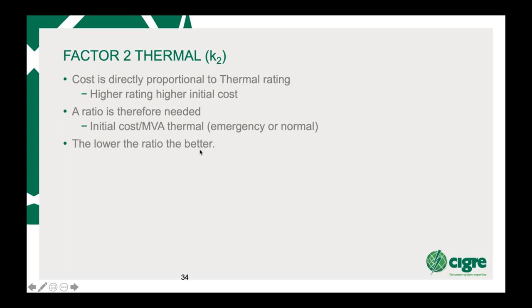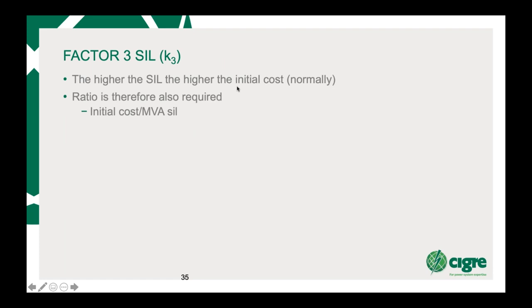Then the third one is surge impedance loading. The higher the surge impedance loading, the higher the initial cost normally. Therefore, a ratio is normally also required. So initial cost to MVA SIL. So the higher the SIL, lower initial cost, better the ratio, better the design.